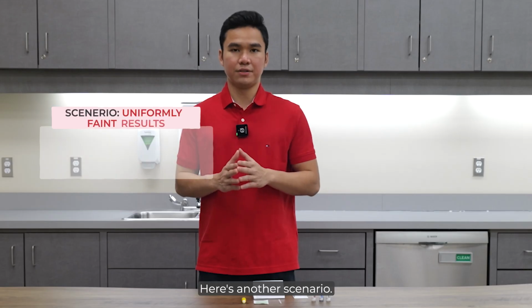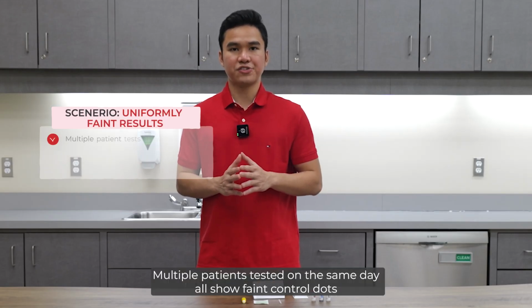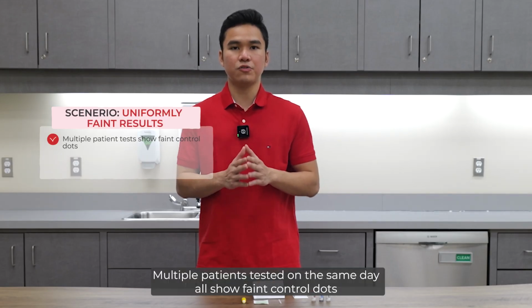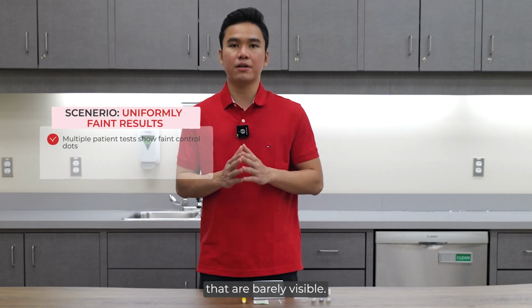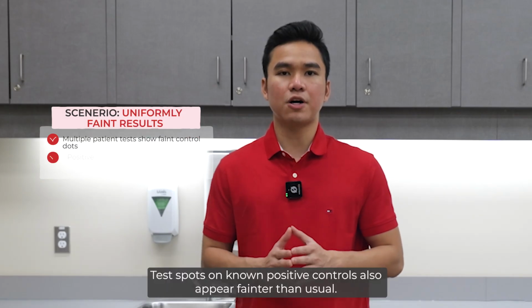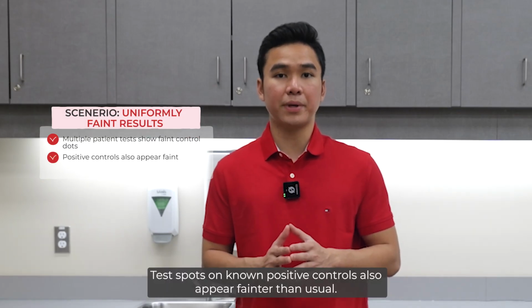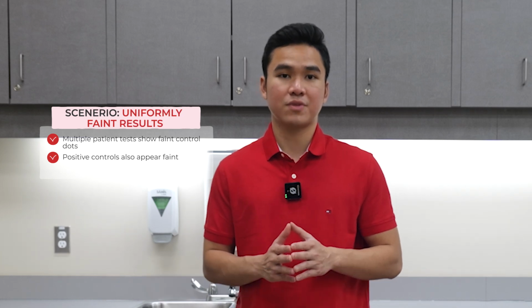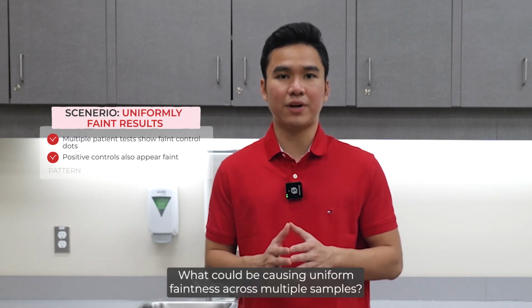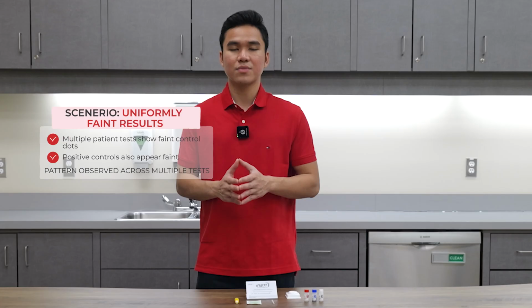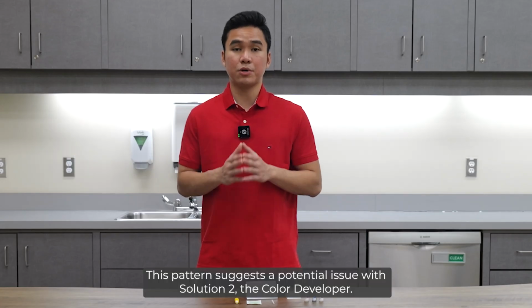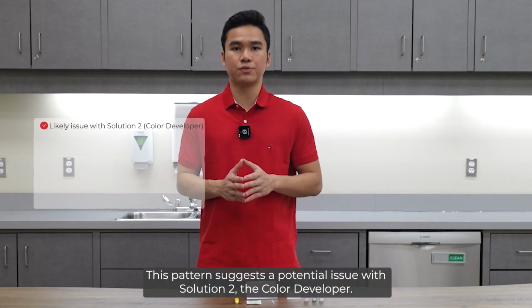Here's another scenario. Multiple patients tested on the same day all show faint control dots that are barely visible. Test spots on known positive controls also appear fainter than usual. What could be causing uniform faintness across multiple samples? This pattern suggests a potential issue with solution 2, the color developer.